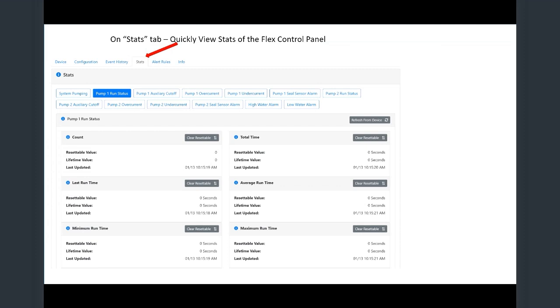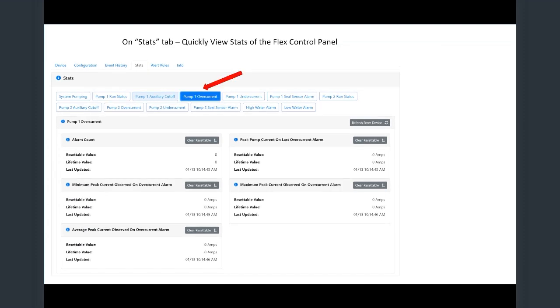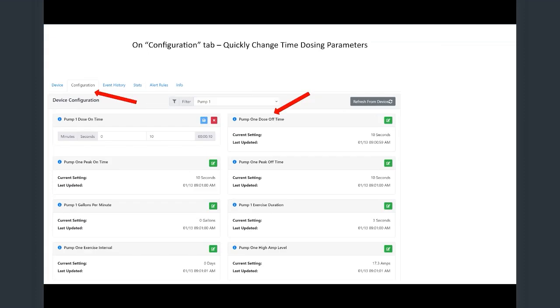And then we have different stats. On the top, there are different tabs. Here's a pump 1 status, and we have your different counts, resettable value, lifetime value, and then it tells you the last time it was updated. So you have run times, average times, max times, things like that. Up on top, you have seal alarms, high water alarms, over and undercurrents, a lot of different data points. You can go in and configure how long you want your dose on and off times to be, things like that.